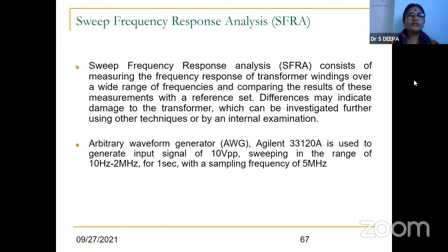Next is sweep frequency response analysis. This is the method. Sweep frequency means usually the frequency will vary with respect to time in a signal. That is called sweep frequency. So for this we need an arbitrary waveform generator. Agilent is used to generate input signals of 10 volt peak to peak, sweeping in the range from 10 hertz to 2 megahertz for 1 second with a sampling frequency of 5 megahertz.